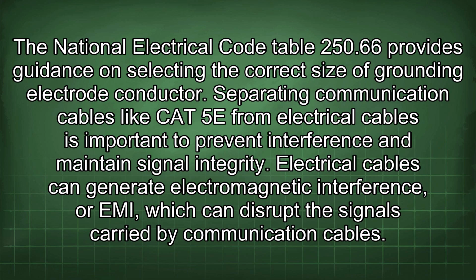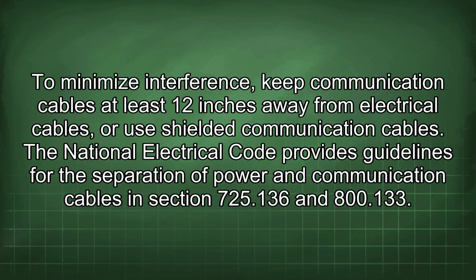Separating communication cables like CAT 5E from electrical cables is important to prevent interference and maintain signal integrity. Electrical cables can generate electromagnetic interference, or EMI, which can disrupt the signals carried by communication cables. To minimize interference, keep communication cables at least 12 inches away from electrical cables, or use shielded communication cables.